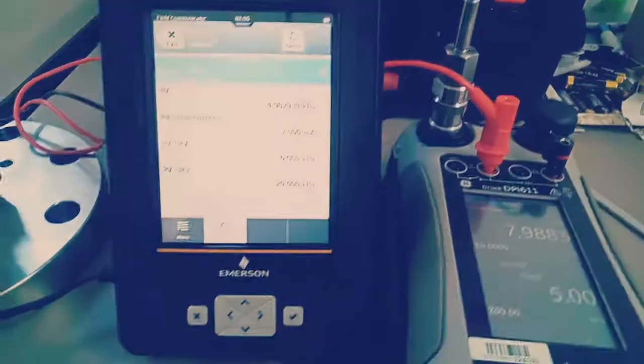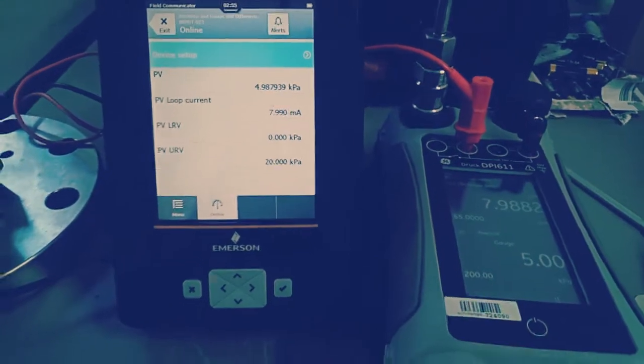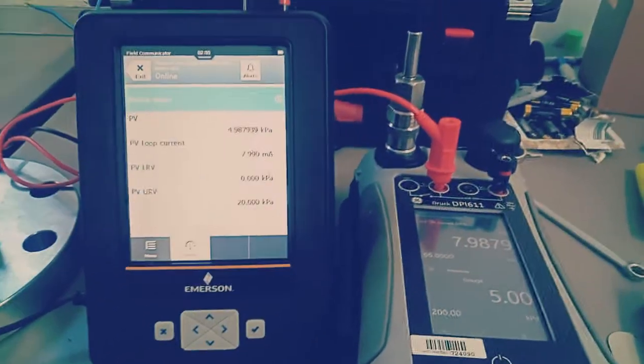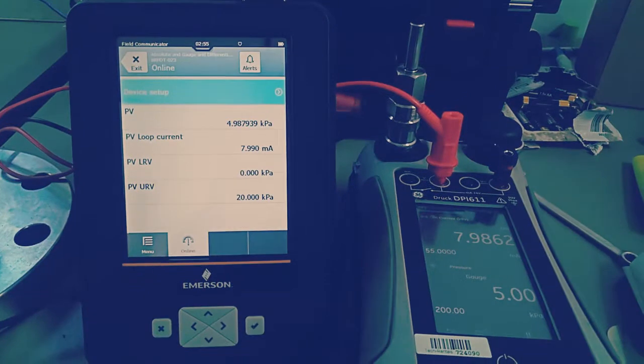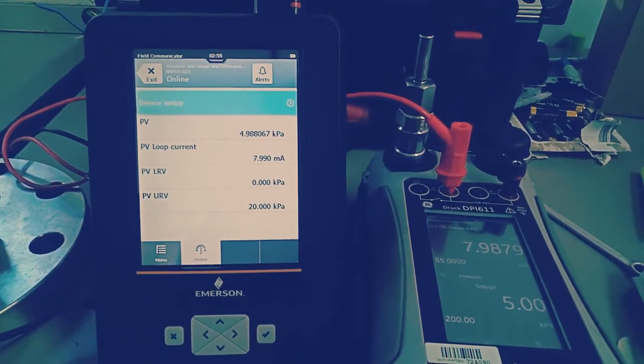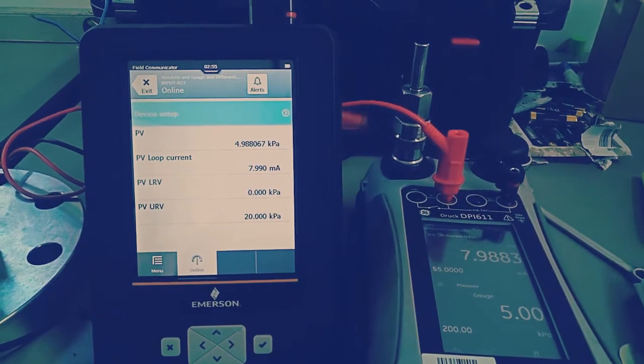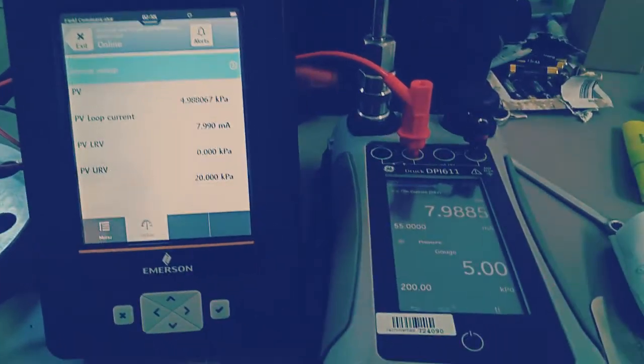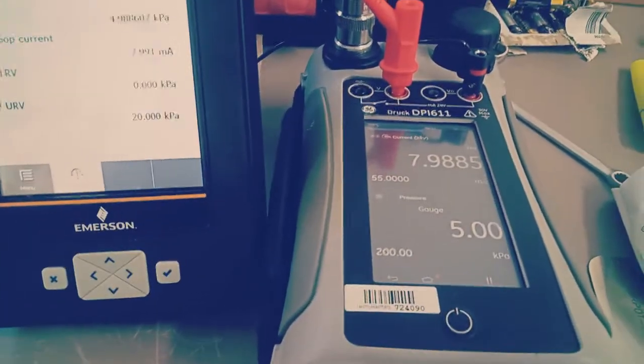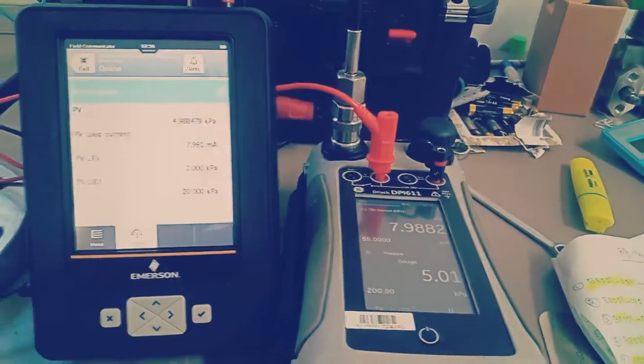This is exactly 5 kilopascal, and what we get is 7.9879, which is below our tolerance, so the value is acceptable. You can see the HART displayed values, the value is 7.99. This is the value for 5 kilopascal, 25 percent, and we go to 50 percent, half of the transmitter capacity.